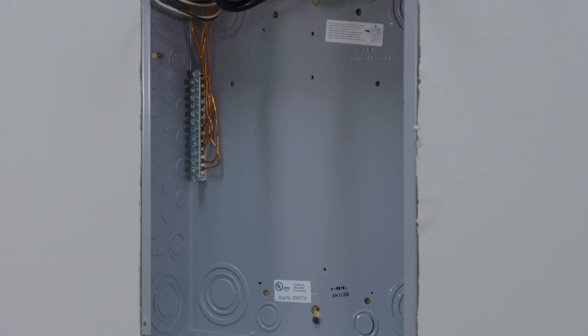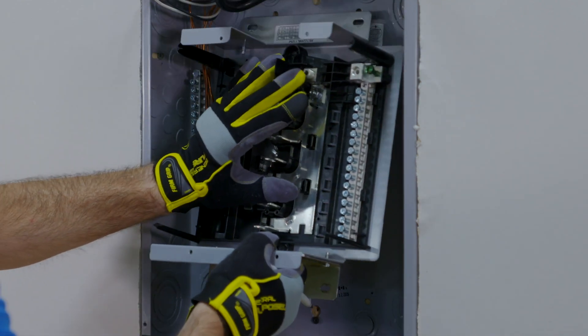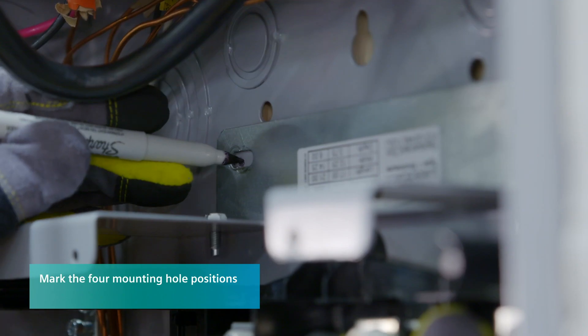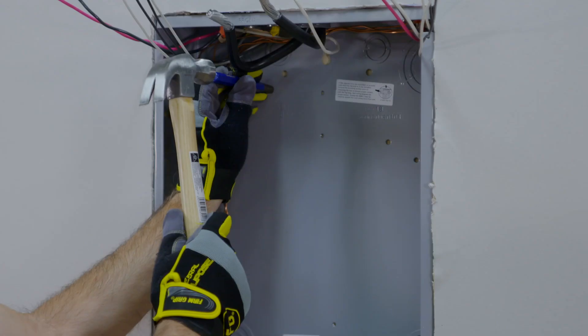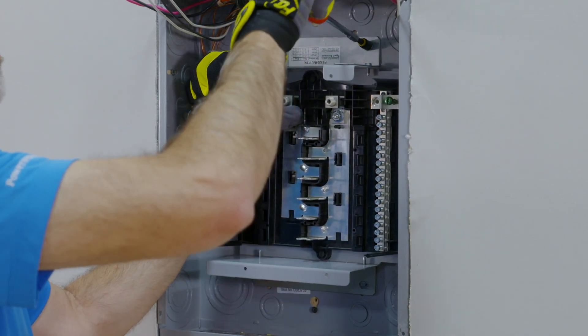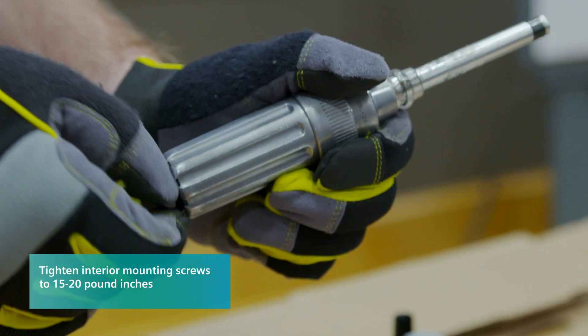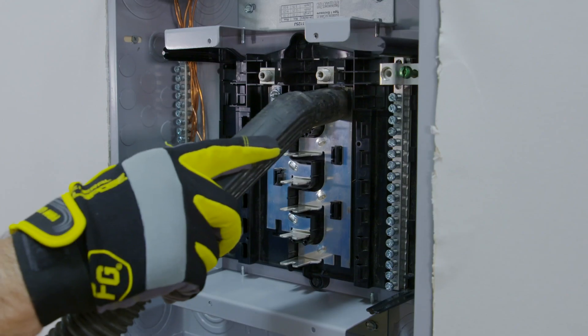Now we'll secure the interior assembly to the enclosure. Position the interior assembly in the enclosure according to the National Electrical Code for wire bending requirements. Mark four mounting hole positions on the enclosure and then remove the interior assembly. Use a center punch and then drill holes using a number 17 drill bit. Secure the interior assembly to the enclosure using the interior mounting screws. The use of a magnetic tip socket is recommended, and torque the screws to 15 to 20 pound-inches. Remember to remove any sheet metal debris from drilling.